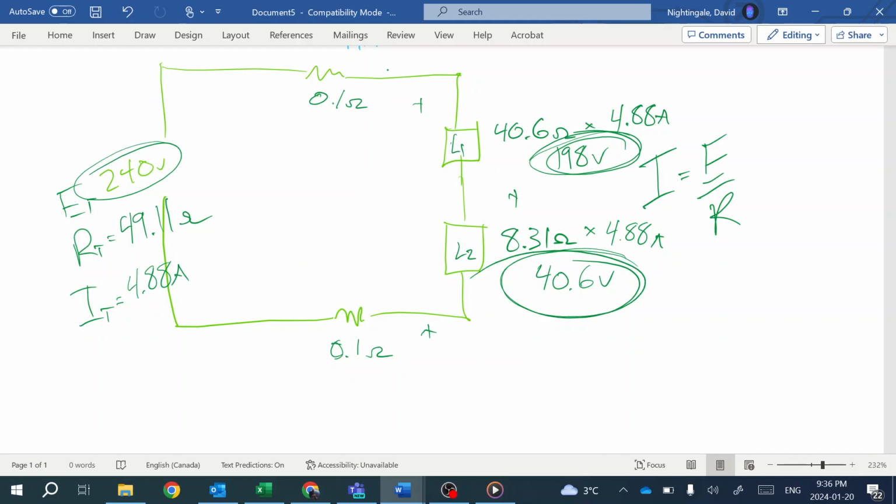We want to maintain that consistent 120 volts on our loads. That's what most loads are designed for. And as you can see, now that the neutral is gone, one load is receiving almost 200 volts, the other one's only receiving 40 volts, and that's going to have a very ill effect on whatever we have plugged in to that circuit.